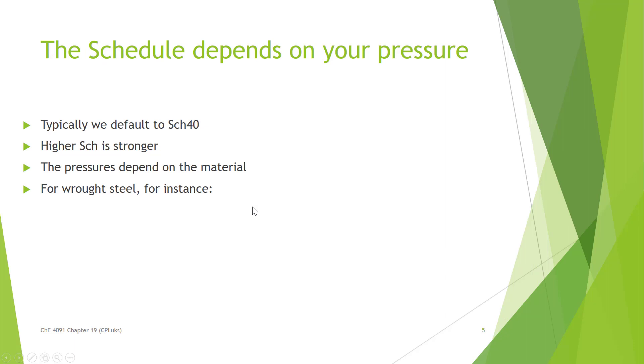Typically we default to schedule 40, which is the standard. You can go to lower schedules like schedule 10 or schedule 5, which tend to be used for things like drain pipes where there is no pressure issue. If you go to a higher schedule — schedule 80 or 120 — then the pipe is going to be stronger, and the pressure it can withstand will depend on the material you choose and the schedule, which reflects the wall thickness.